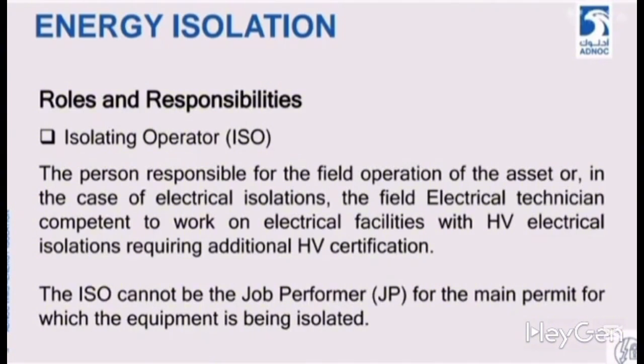If electrical isolation is to be done, then your field electrical technician will be your electrical ISO. The ISO cannot be a job performer. The ISO cannot perform JP work for the main permit on the same permit for which they are the isolation certificate holder. The main permit is the same as the one for which the isolation certificate is being verified, for which the equipment is being isolated.